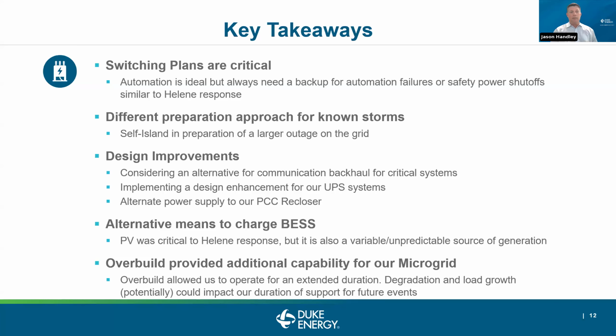We also take a different preparation approach for known storms versus unknown events. For unknown events, like a normal day, power goes out and it operates automatically. In this case, we decided to self-island in preparation for this larger outage on the grid, meaning we disconnected our microgrid from the grid early, because we didn't want any potential reclosing effects or anomalies on the grid to hurt our microgrid. So we went to what's called self-island mode, meaning we were basically taking care of our own power needs within the microgrid, not connected to the grid yet.